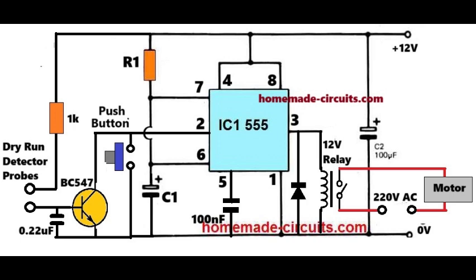As soon as the water supply at the source becomes unavailable, the water across the dry run detector probes is removed, which enables the monostable timer back into action, causing the motor to remain operational for some moments until the monostable time has elapsed, and then the motor pump is automatically turned off.